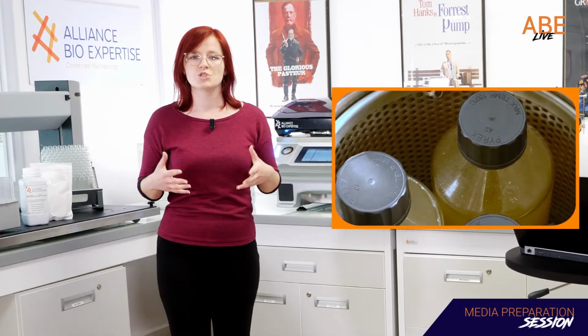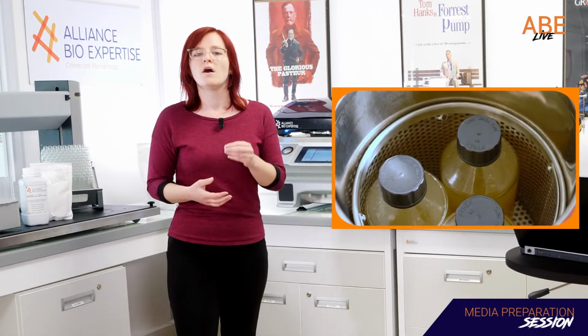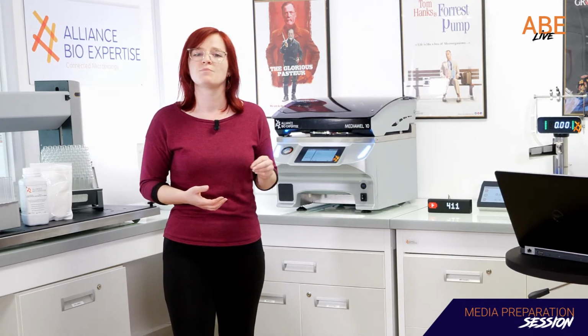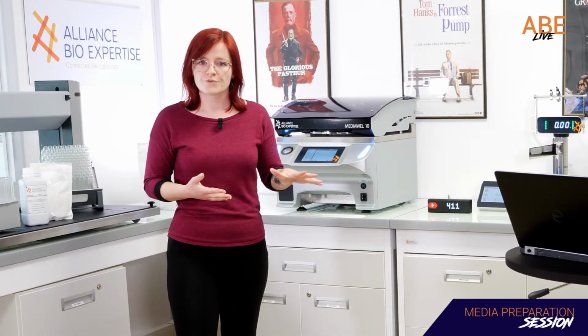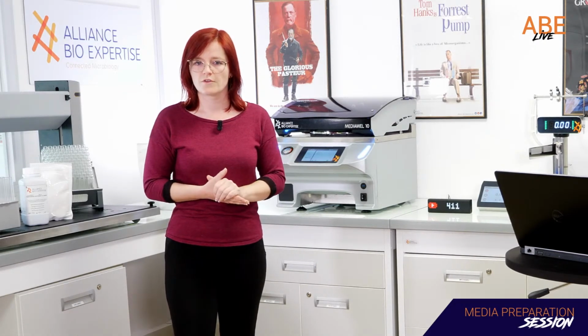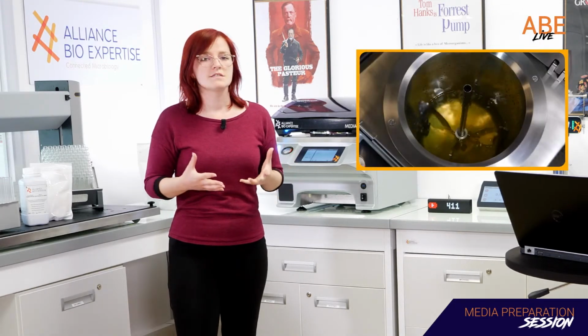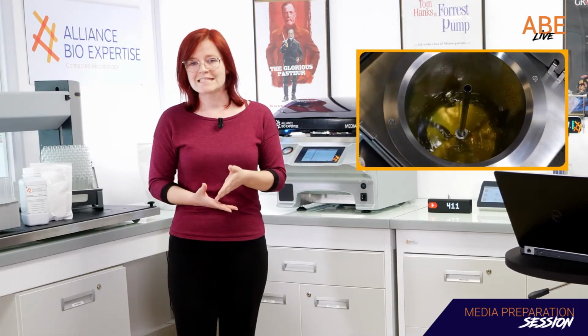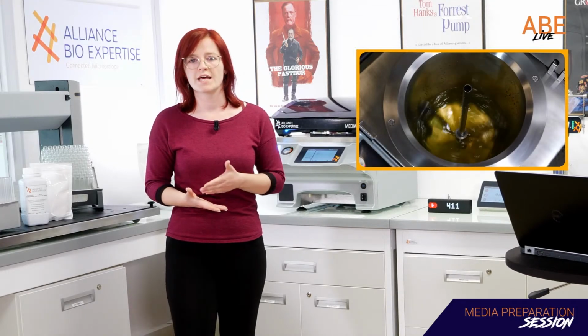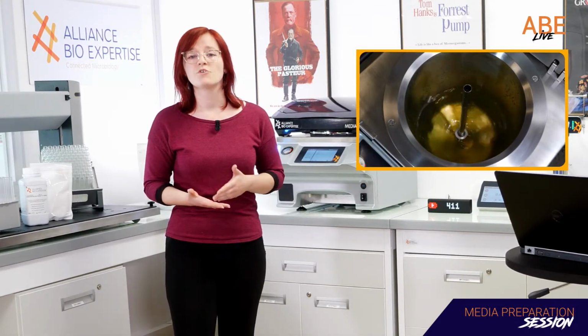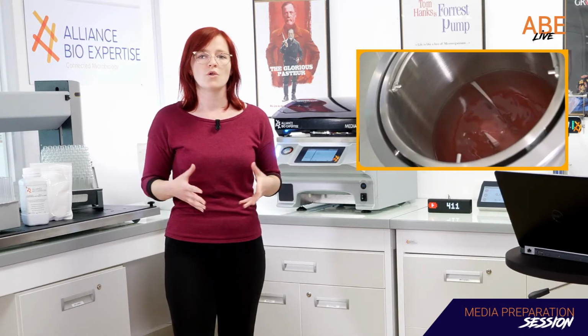And now, what about the media mixing, which is also really important? How does it work in each method? Well, with the autoclave, it's very simple. There is no system to have a continuous homogenization of the media during the cycle. It's not possible to put a mixing system in each bottle. So it will only be done previously with the pot or with the blending. With the media prep, it is different because you have a stirrer inside the vessel which will be able to homogenize the whole media continuously during the preparation, but also during the distribution.